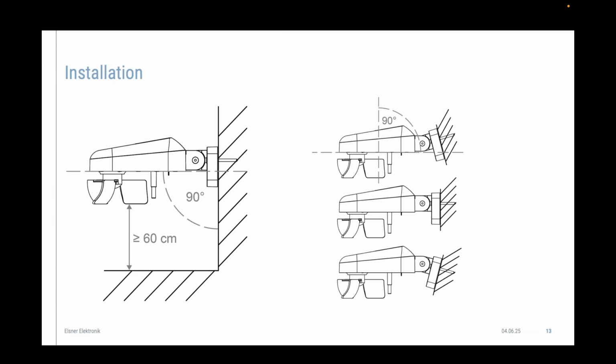It's really remarkable how often we get reports about weather stations that are not working. In most cases we receive the weather sensor back, we test it, and have to say it has the full functionality. And this often leads to the fact that we need to check how the sensor is mounted. You often see there's an AC below the weather sensor, for example, which will create some wind and will make the exact wind measurement very difficult.